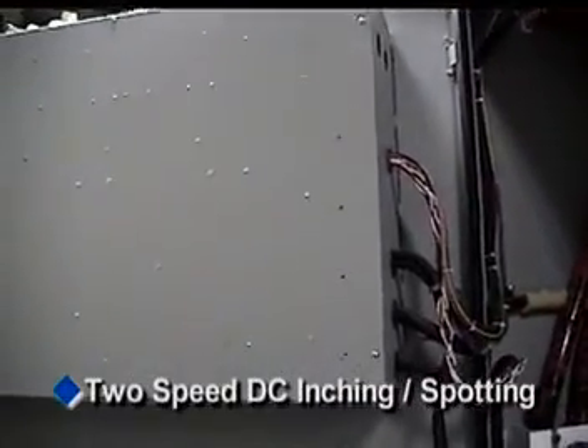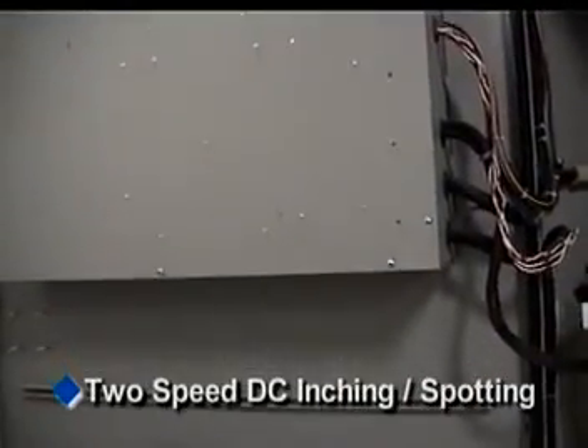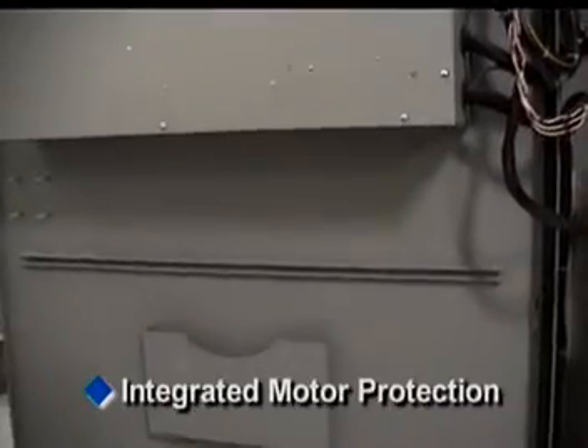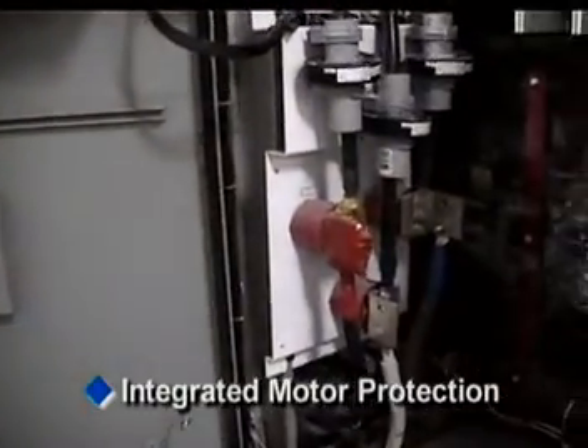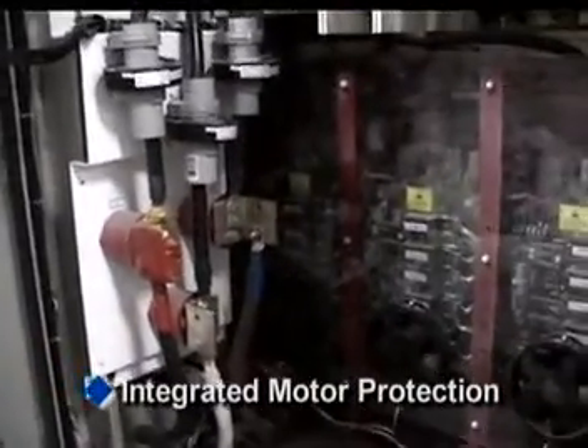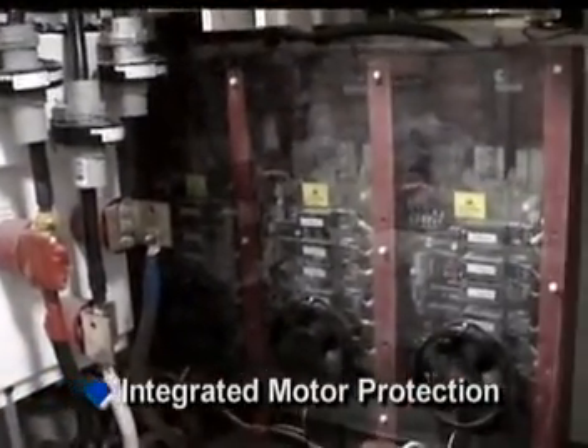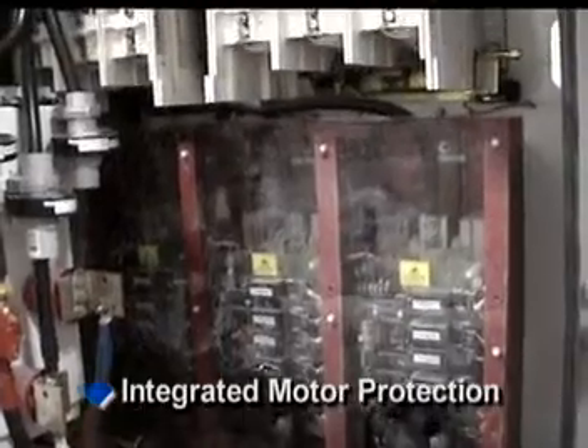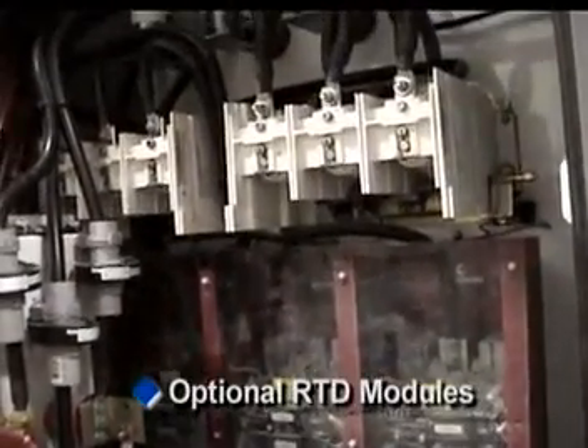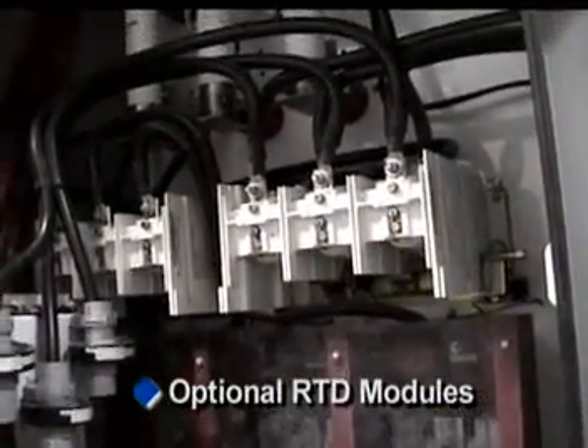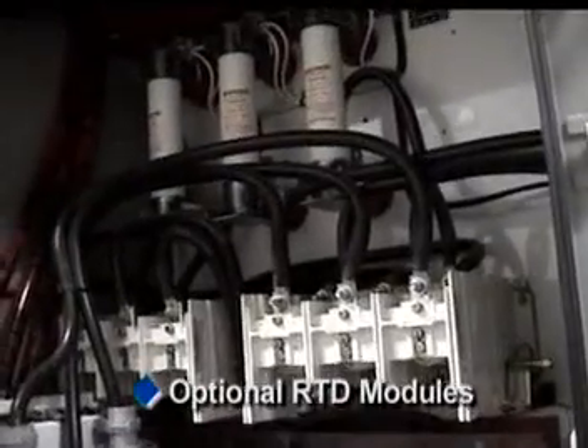2-speed solid-state DC inching is provided for 2 and 10% motor base speed, forward or reversing rotation, and includes adjustable current limit and inch time protection. Standard Benshaw Micro 2 motor protection includes solid-state overload, under and over voltage, over/under current, single phase and phase loss, synchronous field pull-in and pull-out protection.